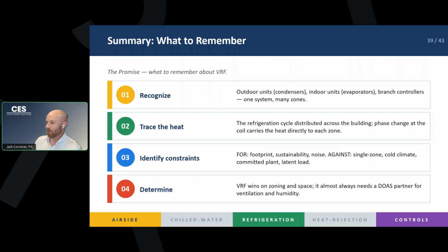Next, we learned about how we actually transfer the heat with this VRF system, right? We're still moving our heat from the indoor space to our ambient air. And how do we do that? That's with the refrigeration cycle. VRF spreads that refrigeration cycle throughout the building, running refrigerant between an outdoor unit and an indoor unit. And as you can remember, we are manipulating pressure, right? Our pressure dictates our temperature. And by varying our compressor speeds and our expansion valve, we are changing our pressure and getting different capacities at our zones. So our controls loop, our VRF and refrigerant loop, and our air side loops are all working together in order to get a very energy efficient solution here.